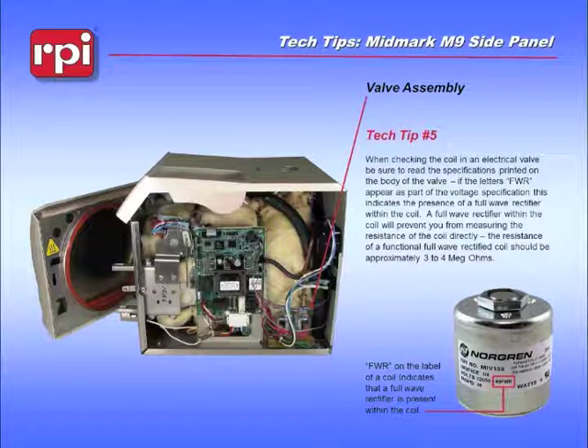Now, Midmark made their valves in two different styles. The way they changed them over the years was they installed internal to the coil a full-wave bridge rectifier. These valves run at 120 volts AC. If you install a bridge rectifier within the coil, you immediately take that AC and convert it into a DC voltage, and that means that the internal parts to the valve are different.